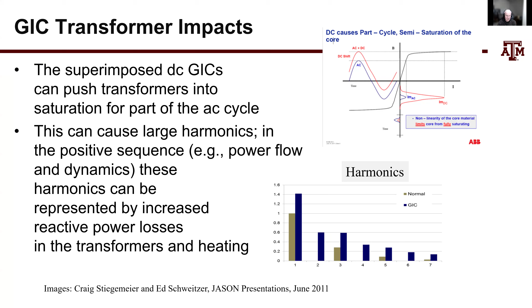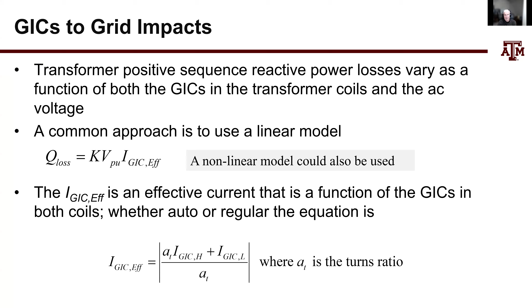This is a slide I use in my GMD presentations, but it's pretty much the same for HEMP. Once you get the GICs, they cause a reactive power loss in the transformer, and that loss varies as the GICs vary. During an E3 event, the GICs vary pretty rapidly over the course of several minutes.